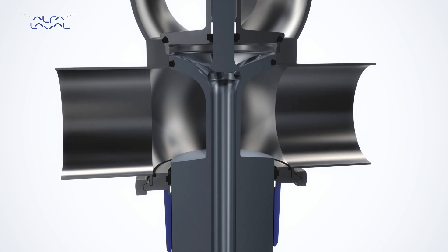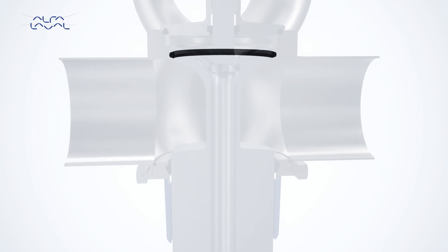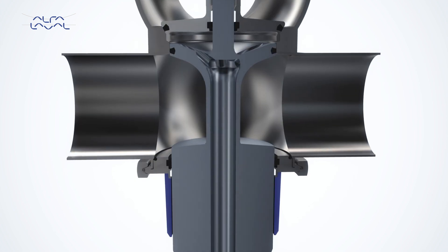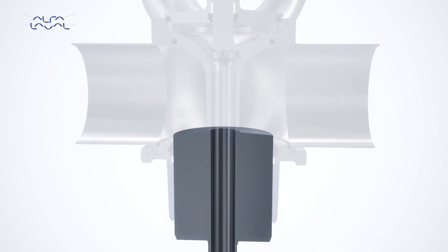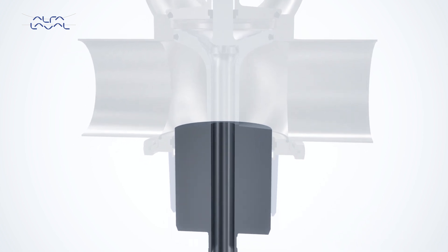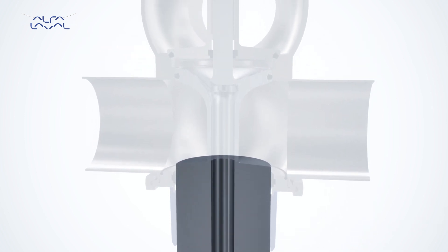The lower plug features a guided and protected radial seal, which provides long-lasting operation. The lower plug is always supplied hydraulically balanced to ensure that the mix-proof security and excellent hygiene capabilities of the valve are not jeopardized in the event of pressure shocks in the process pipe.